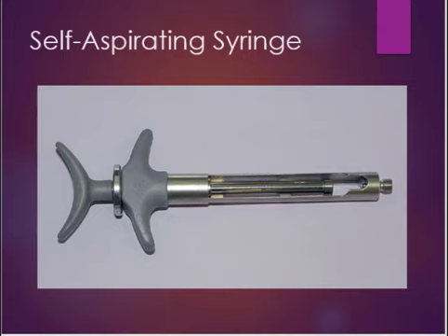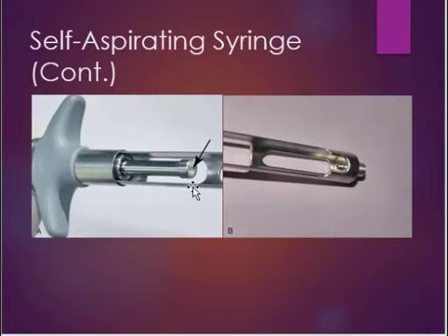And the way that negative pressure works, it's achieved by a metallic sleeve surrounding the needle and resting on the rubber diaphragm in the cartridge. This is what it looks like. Again, it doesn't have a harpoon attached to the piston. The metallic sleeve of the self-aspirating syringe is located at the base, and it comes into contact with the diaphragm of the cartridge, and it stretches it to produce that negative pressure of the cartridge during the aspiration test.